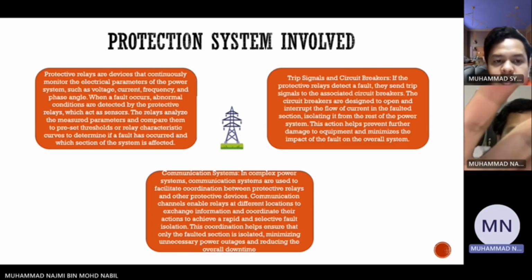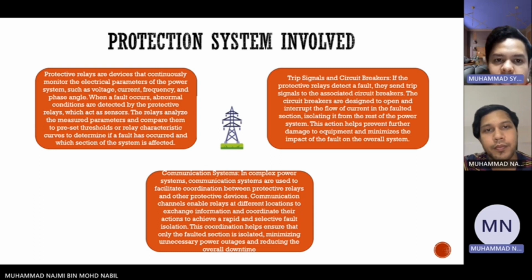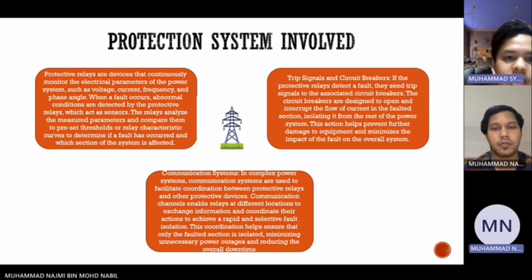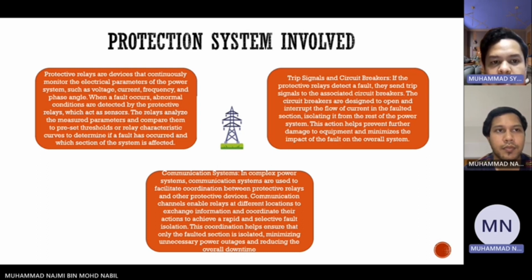emergency incident. Okay, my name is Muhammad Sharifuddin bin Asmadi. I will explain about the protection system that was involved in this incident. First of all, protection relays are devices that continuously monitor the electrical parameters of the power system, such as voltage, current, frequency, and phase angle. When a fault occurs, abnormal conditions are detected by the protection relay, which acts as a sensor. The relay analyzes the measured parameters and compares them to preset thresholds or relay characteristic curves to determine if a fault has occurred and which section of the system is affected.